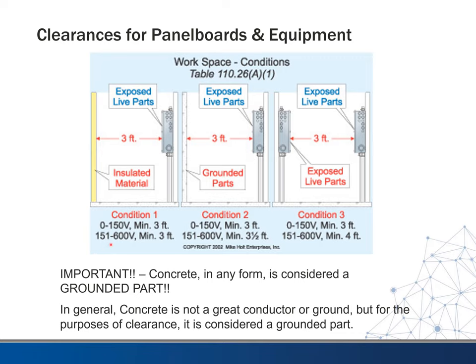When you get up to the higher voltages, which would be our 208 or our 480 volt services, or anything that's three phase, will fall in the bottom line. You can see you can go 3, 3.5, and 4 feet here, okay? So one thing to keep in mind, and most people don't realize this, is when you have concrete, which is commonly the case on the other wall, technically, as far as the code's concerned, that's considered a grounded part. It's not an insulated material.